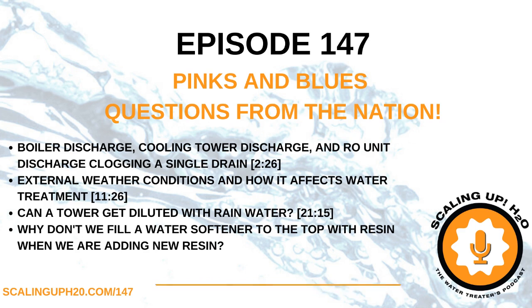Well, we fluff it up, we get rid of all those little channels if there are any. Remember, water always goes to the path of least resistance. So if that resin bed is not packed down well and there's some weak areas in that resin bed, that water will channel each and every time. Now, this is the reason that we want to fill the resin to only 66%, not 100%, 66%, because it gives us that headroom space to fluff up the resin, and that is so important.